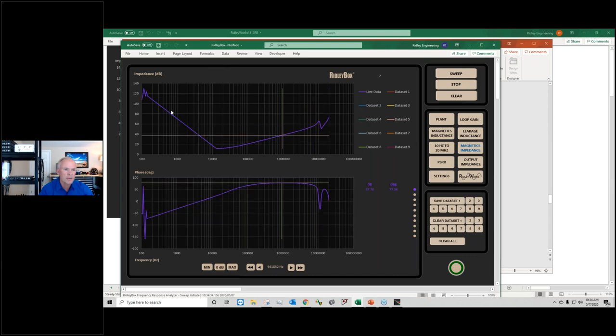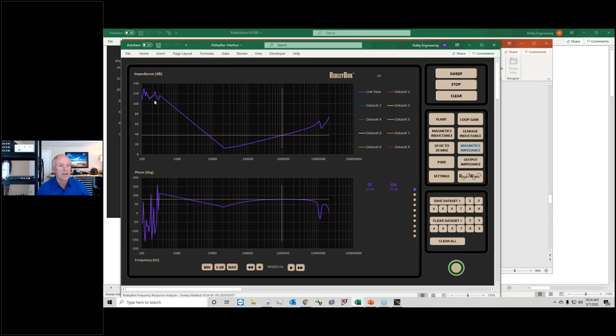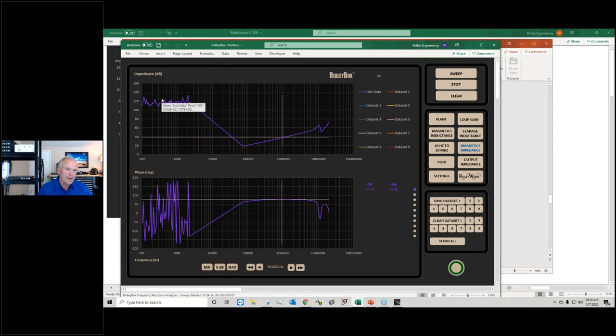So right now we're just sweeping at the limits of this particular analyzer, somewhere around 110 dB—it's pretty good. Then when the impedance of the cap drops below that 100 dB, 110 dB level, we will start seeing the capacitance. Hopefully that's connected, I think it is. And there we go, you start seeing that coming down now at high frequencies.